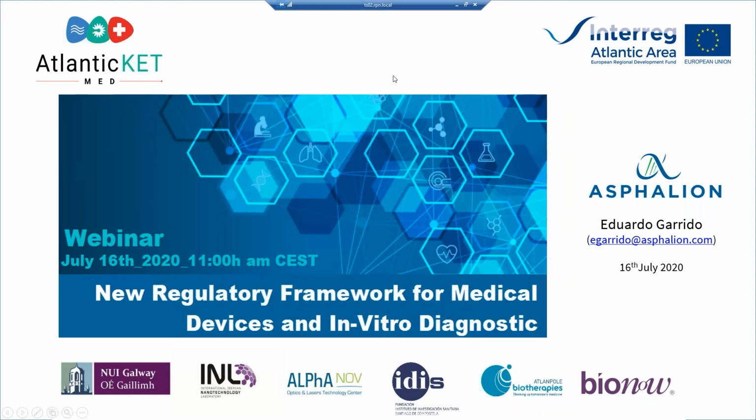Okay, but yes, if several rules apply, you will have to follow the higher risk one, which would be class 2A. So you'd have to undergo the certification with a notified body.